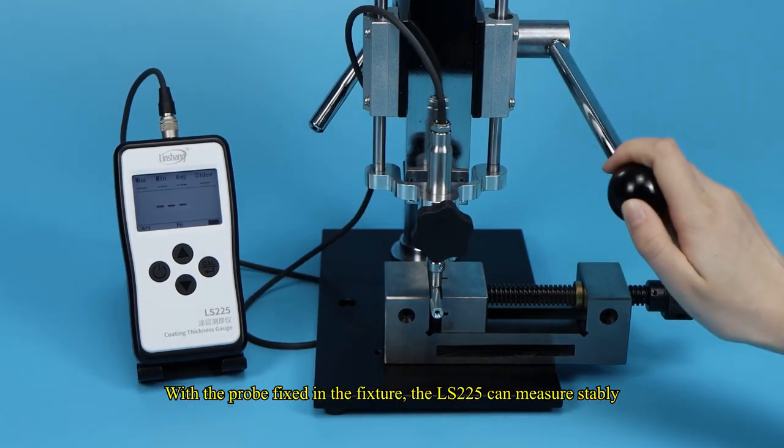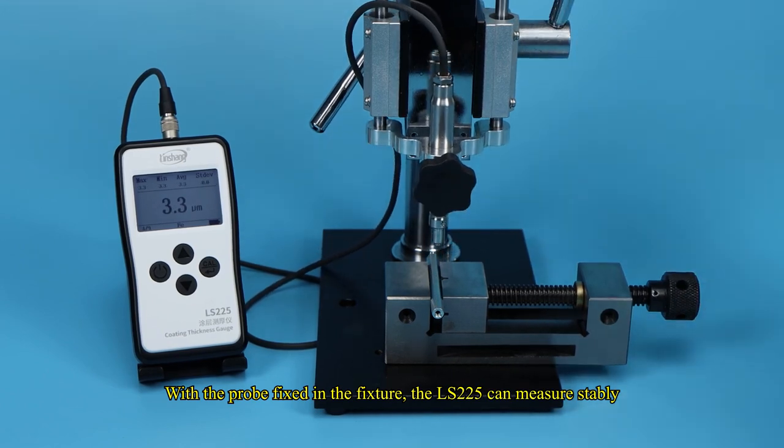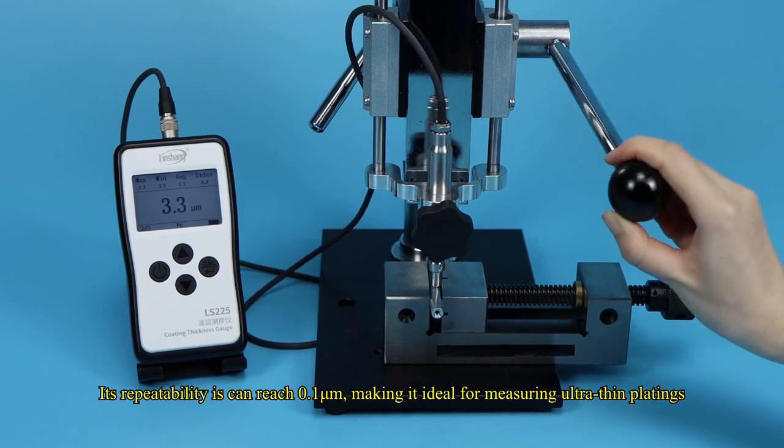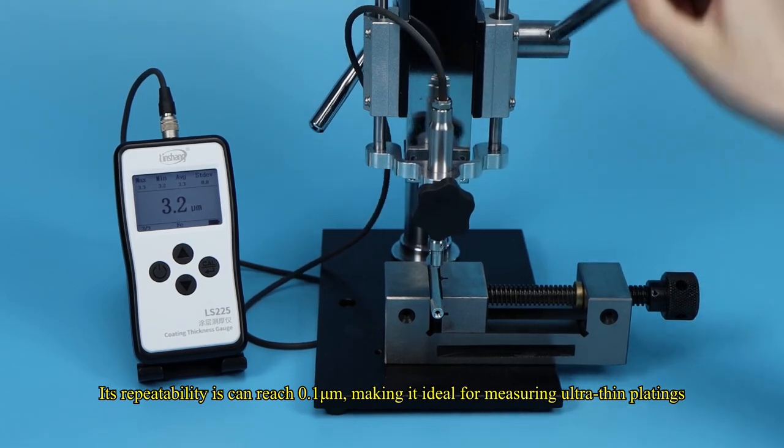With the probe fixed in the fixture, the LS-225 can measure stably. Its repeatability can reach 0.1 micrometers, making it ideal for measuring ultrathin platings.